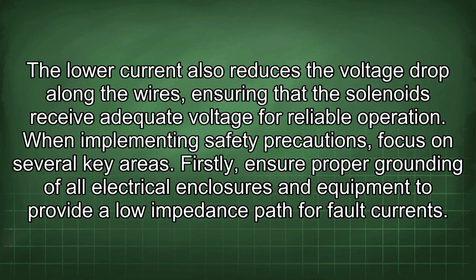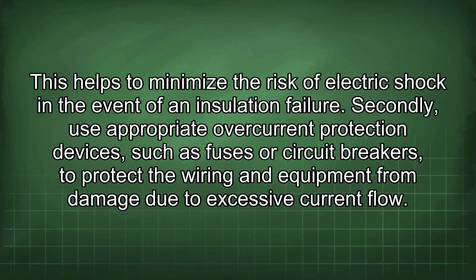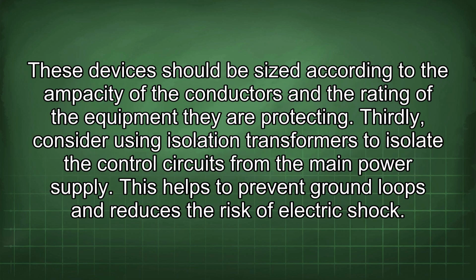Firstly, ensure proper grounding of all electrical enclosures and equipment to provide a low impedance path for fault currents. This helps to minimize the risk of electric shock in the event of an insulation failure. Secondly, use appropriate overcurrent protection devices, such as fuses or circuit breakers, to protect the wiring and equipment from damage due to excessive current flow.